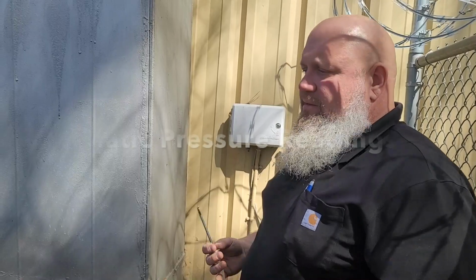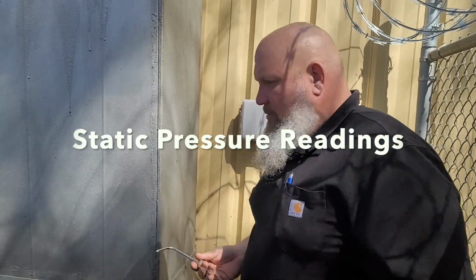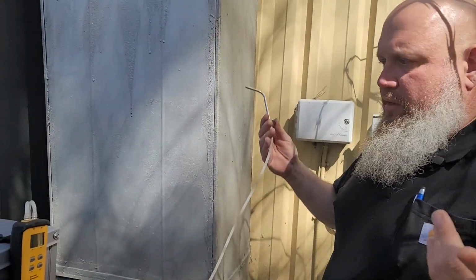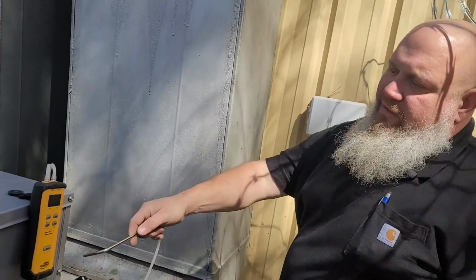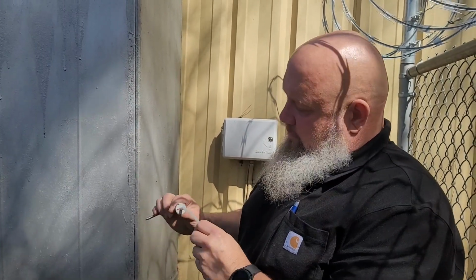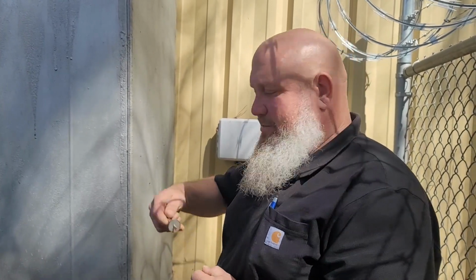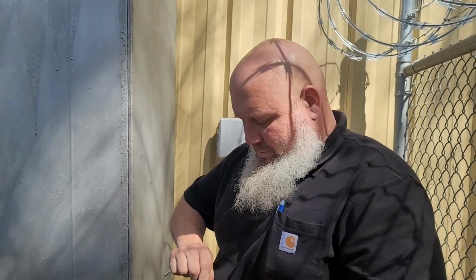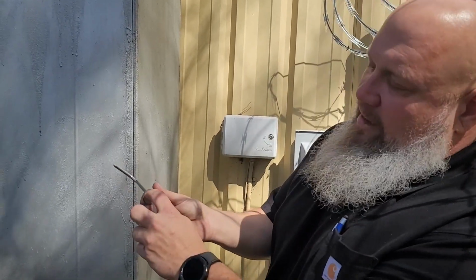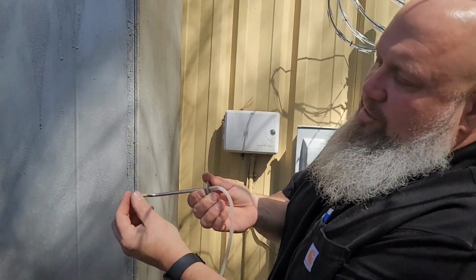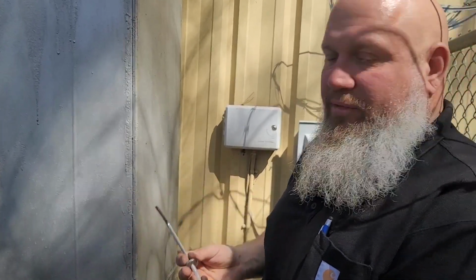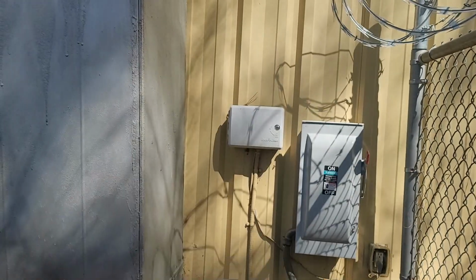Yep. We're about to take the static pressure readings, and I use this FieldPiece that's got two tubes, so it'll give me the actual difference, your total static pressure. And when you're doing it, there's an arrow, and the arrow actually points into the airflow. I know most people think it points against the airflow, but that's not the way it is. You've got to make sure that arrow is pointing into the airflow, so these two tubes can pick up the proper static pressure reading. Excellent.